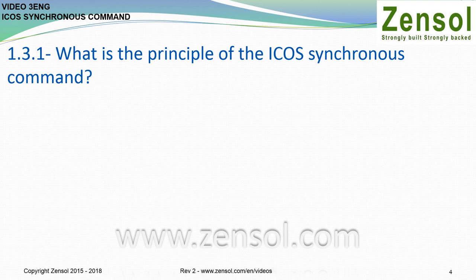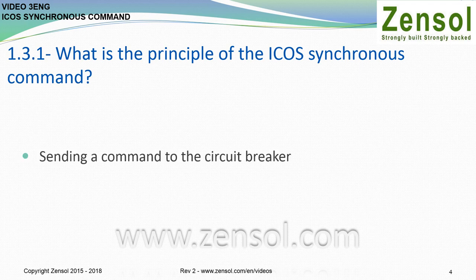ICOS is a French acronym meaning Synchronous Order Command Interface. It is a controlled switching device that sends an open or close command to the circuit breaker to synchronize its operation. ICOS is used only during controlled operations, which means during intentional operations.